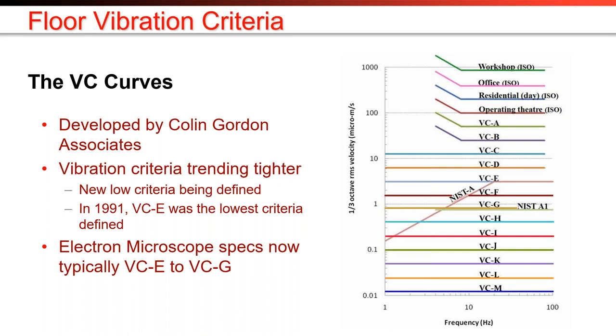There is a set of curves called the VC curves, or vibration criteria curves, developed by vibration consultant Colin Gordon Associates. The goal was to create a common language so that tool manufacturers creating specifications could communicate with lab directors, architects, vibration consultants, and solutions providers. These curves have evolved to the point that ultra-sensitive instruments typically use one of the VC curves as their vibration criteria.